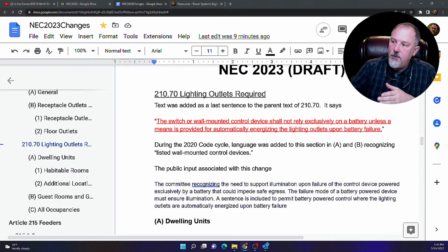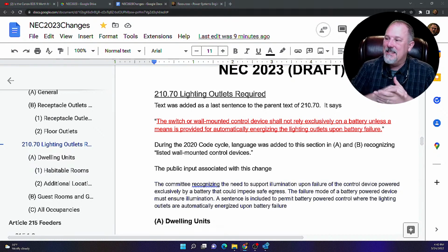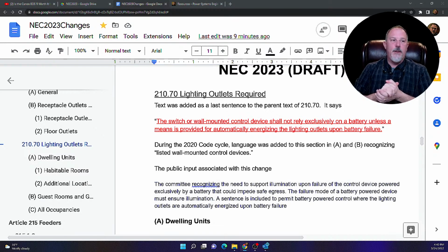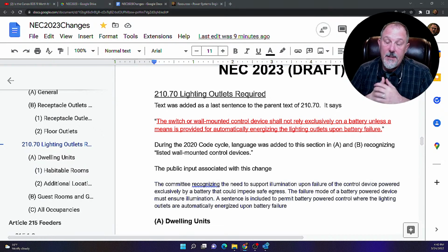But what panel 2 said was the switch or wall-mounted control device shall not rely exclusively on a battery—I like that—unless a means is provided for automatically energizing the lighting outlets upon battery failure. That, to me, is a safety concern. I'd love to hear your opinions on it.